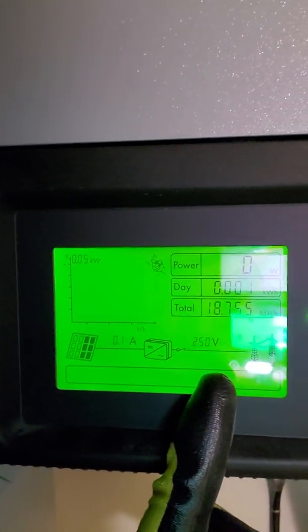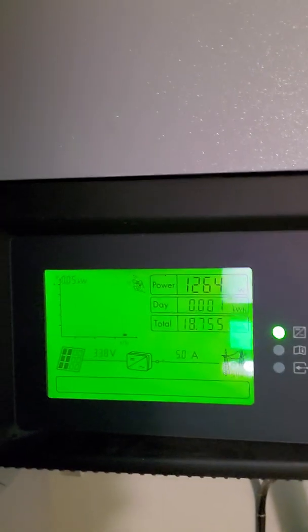You can see on the display, it's also cycling through all of the DC information, as well as all of the AC information right there. All right, and you can see right here, it is making power. Right now it's making 1245 watts. 1.2 amps on the DC side, 5 amps on the AC side. So this inverter is back up and running. And that's how you clear an electrical arc fault.